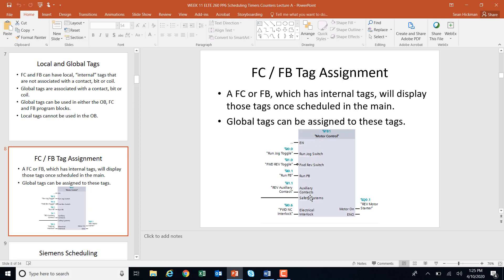Here is a function block that's scheduled. These are my internal tags — run, auxiliary contact, safety, whatever. These are local internal tags because there's no IO on them. You could use global tags inside if you wanted to, but these auxiliary contacts are internal local tags. What we've done is tie the reverse auxiliary contact and the actual global tag to this internal tag. So we could take this motor control and schedule it again and again — reverse motor starter, forward motor starter, reverse starter for motor 2, 3, or 4 — and the auxiliary contacts and run pushbutton would map to whichever real input or output we wanted.